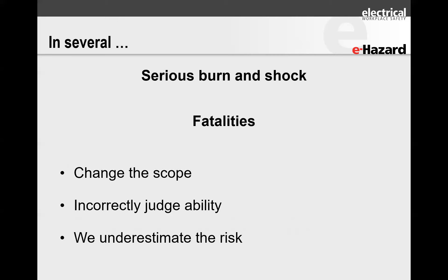We have done several accident investigations. I've been an expert witness on these, and I've learned that serious burn injuries, shock, and fatalities occur through three main drivers. They are: a change of scope, incorrect judgment, and underestimating the risk. Think about these carefully. Change of scope — I may go in to find an overload that's not resetting, open up the panel, and find a loose wire. I've got a screwdriver, so why come back? Why not just tighten this? Have you really stuck to your scope, or have you changed it?